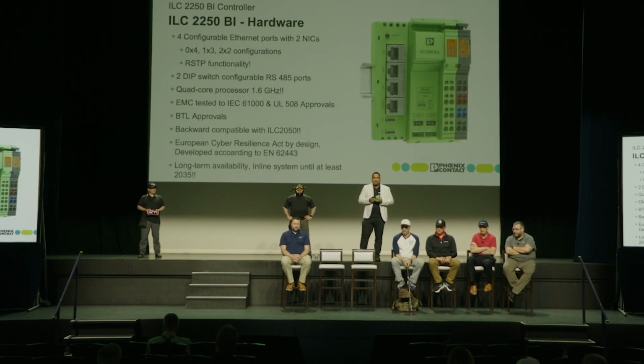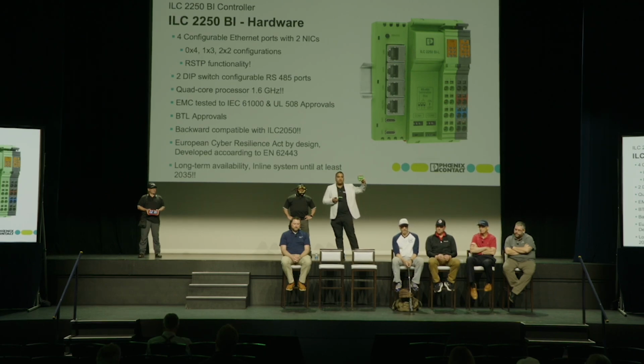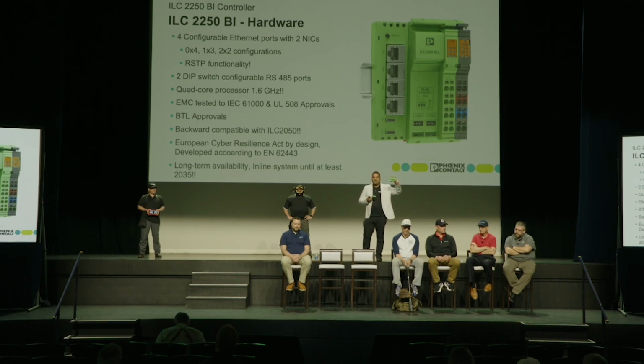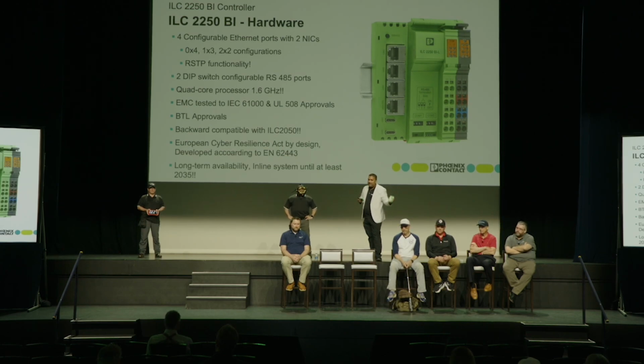Let's talk a bit more about the controller. There are 4 Ethernet ports, and as you can see, there are 2 NICs, 2 network interface cards, in that port. So you can configure each of the 4 ports individually, as a standard Ethernet switch, in a 1 to 3 or 2 by 2 configuration. RSTP is also built into this controller - true rapid spanning tree protocol, the media redundancy you need for your project.